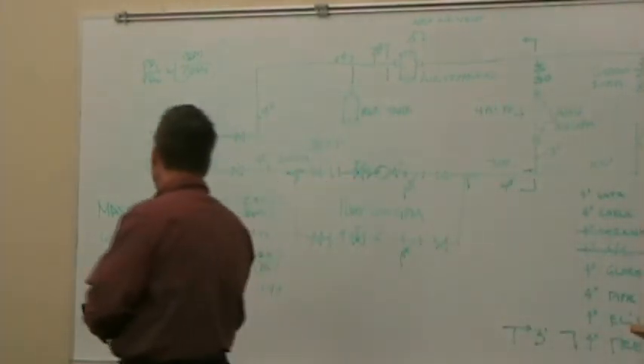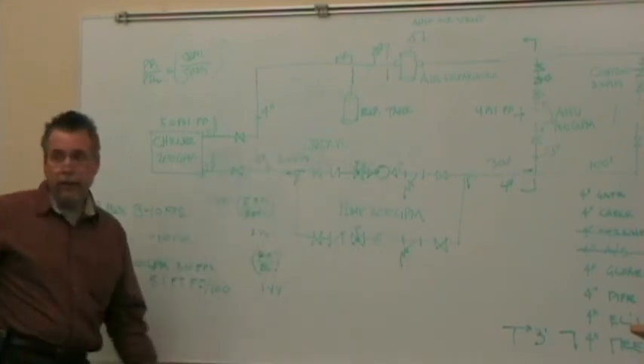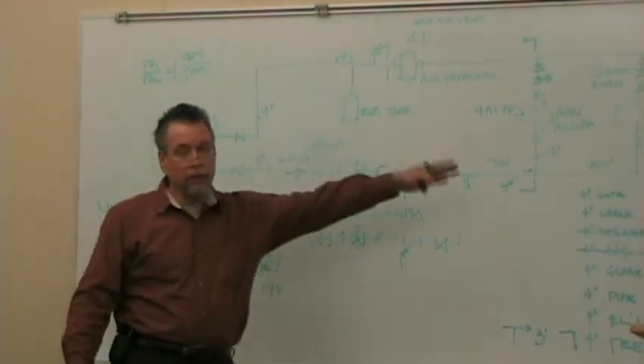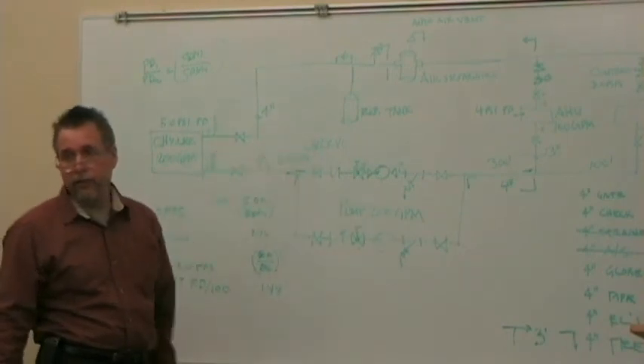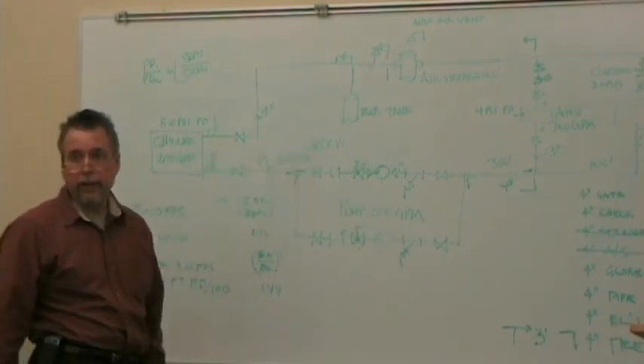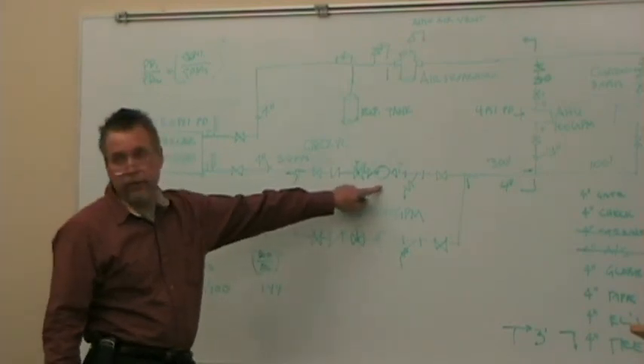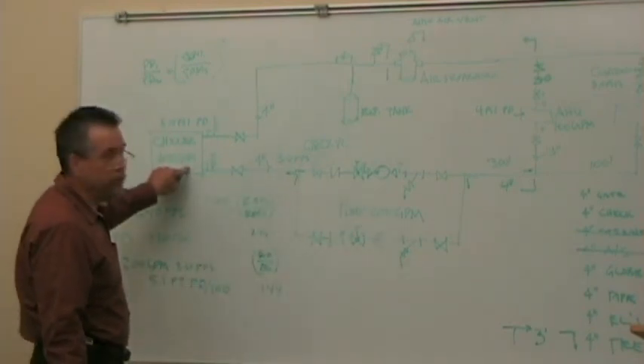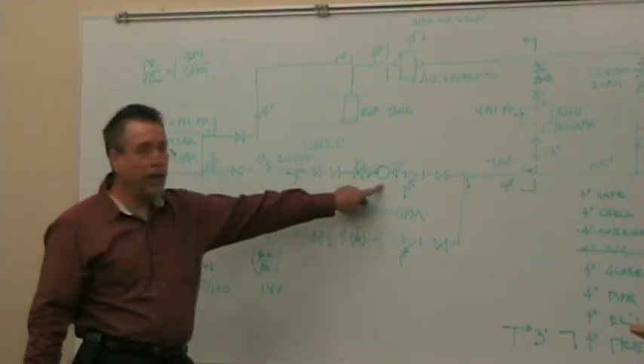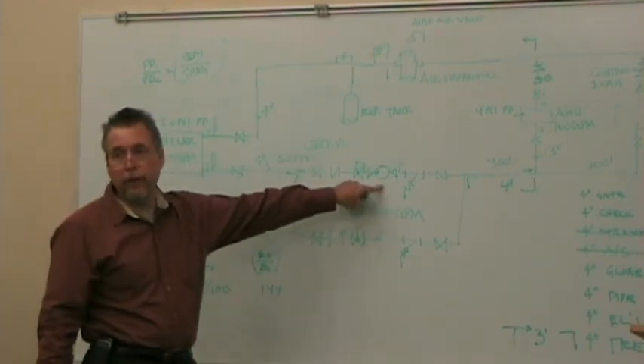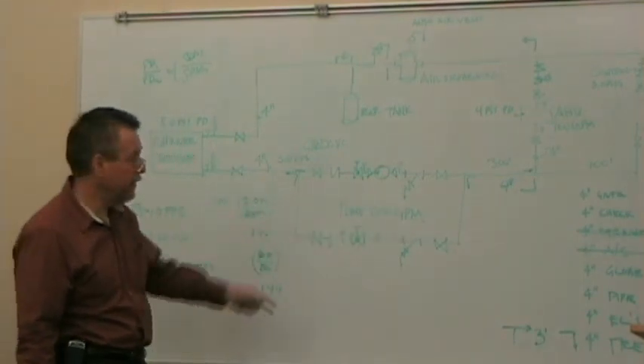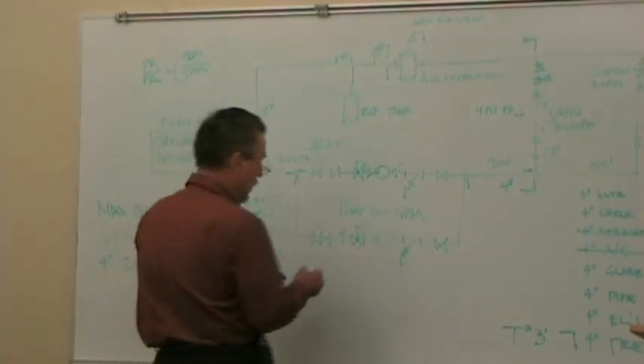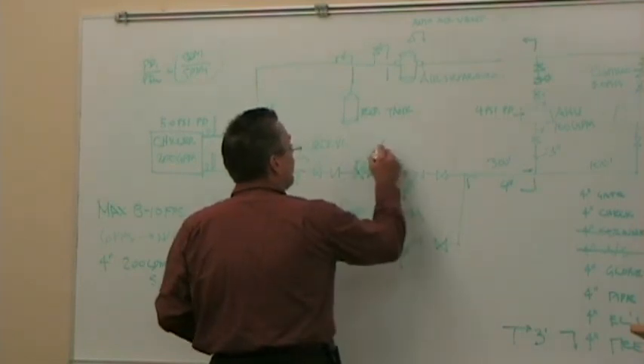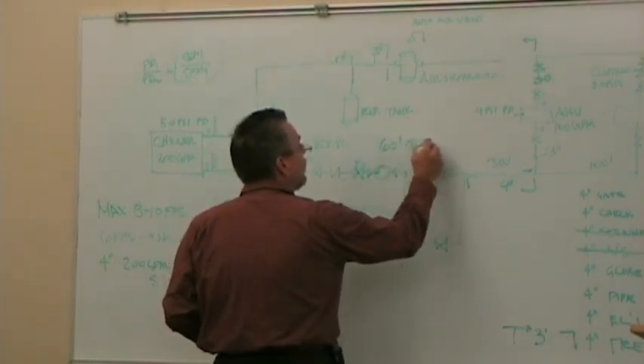So again, all I need to know is what the original conditions were and then measure the pressure drop. And I can calculate what your flow should be. But I don't know how much pipe, I don't know all the fittings, I can't predict the system loss without actually going in and calculating. I mean, I can know what the system loss is, because if I can measure the flow here, I can measure the head here and compare it to what is originally designed. For instance, we're designing our pump at 60 feet of head, 60 feet at 200 gallons per minute.